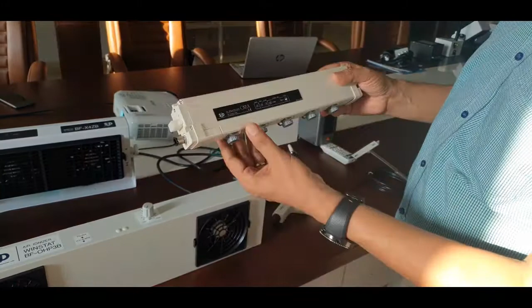The ion bar gives a lot of alarm functions, or maybe you can select the alarm for the cleaning. For example, you want cleaning after so many days, you can set that, and it will give you the alarm that now it is time to clean. Okay, so this works on not very heavy power supply. It works on a simple mobile type charger, 24 volt. Same is here, all with the small chargers.